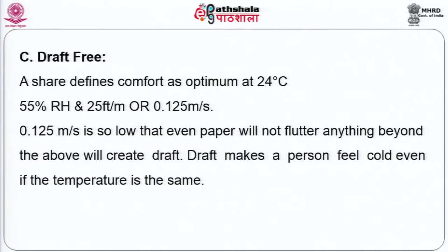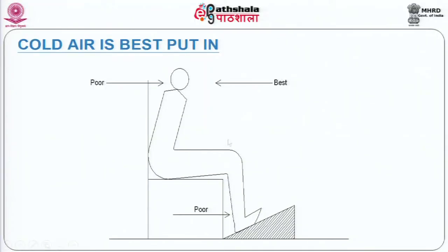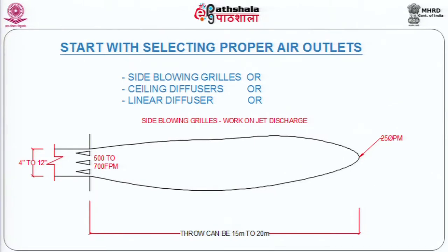If it is higher than this, people will tend to feel cold and they would complain or they will perhaps not be able to complain and will have to sit and bear it for the entire period when they are in the auditorium, which is not healthy. Now, when you talk of draft free, it also means the designer should be very clear about where the air is best required by a person. The ideal is right in the face. The poorest is right on the neck, perhaps equal to having something on the ankle. So, in other words, having air at the ankle and having air at the nape of your neck is perhaps the last thing that you should look for in an auditorium. So, in other words, to get draft-free air, you must know the type of air outlets that are available in the armory of an air conditioning engineer.